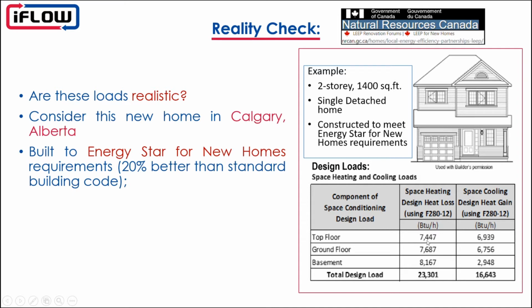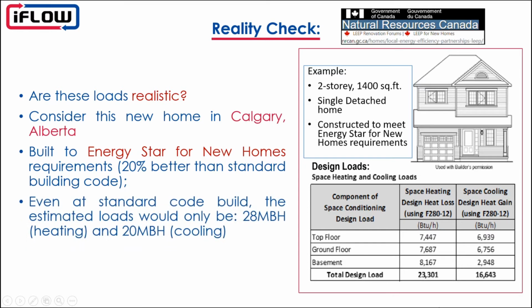You can also see how it's distributed across the house, with the top floor, the middle floor, and the ground floor needing about the same amount of heating and cooling, whereas the basement needs a lot less cooling in the summer and more heating in the winter. Even if we were to build this home to standard building code, that would be 20% less in terms of efficiency. But if we add 20% to the heating load, that would be 28,000 BTUs of heating, and 20% on top of the cooling would be 20,000 BTUs of cooling. So still under 2 tons of cooling and 28,000 BTUs. It's still very low compared to the distribution that we saw, and in line with those numbers.